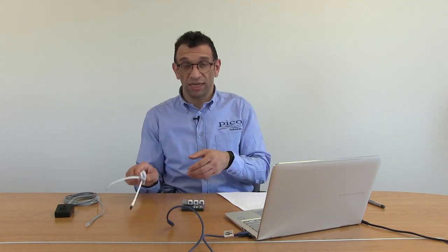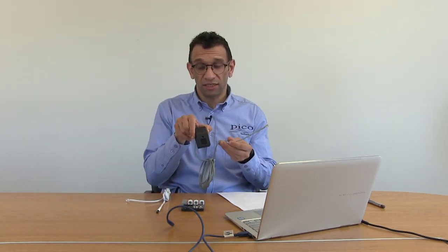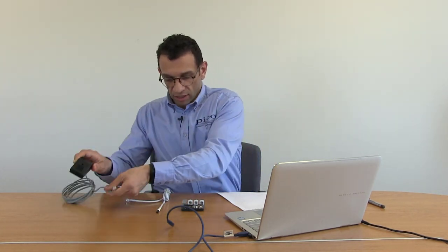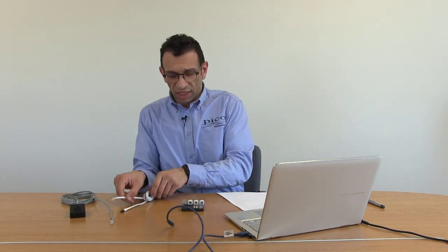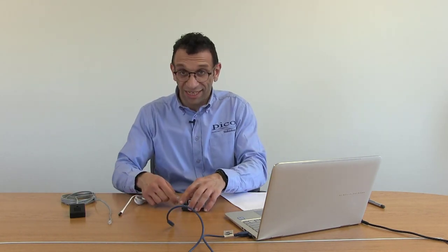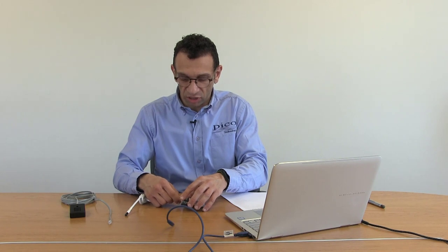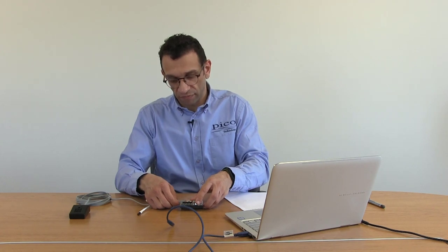In this video, we'll be using the DD 100 temperature sensor and the DD 101 humidity sensor to calculate dew point. Dew point is the temperature at which air is saturated with water vapor. If the temperature drops below dew point, water will condense on solid surfaces. We'll be using input 1 with the DD 100 temperature sensor and input 2 with the DD 101 humidity sensor.